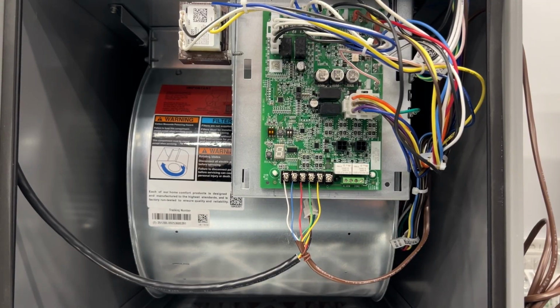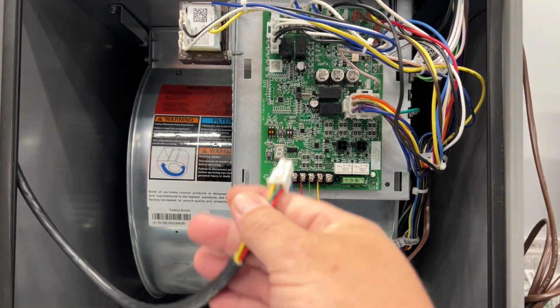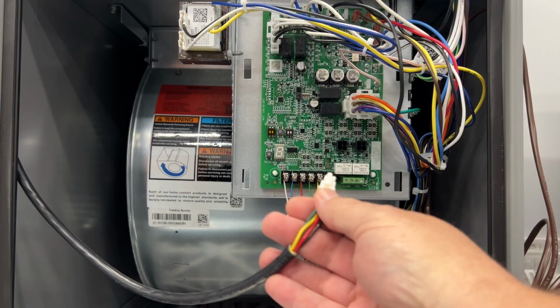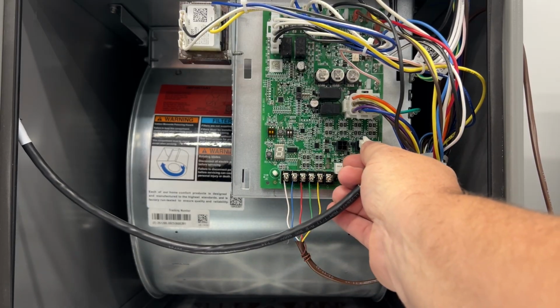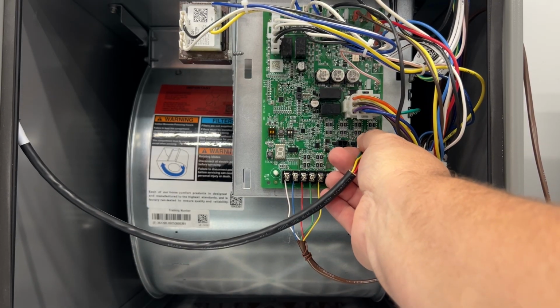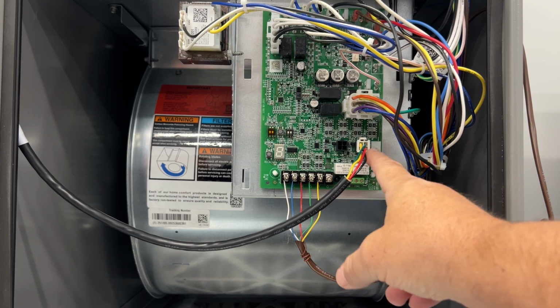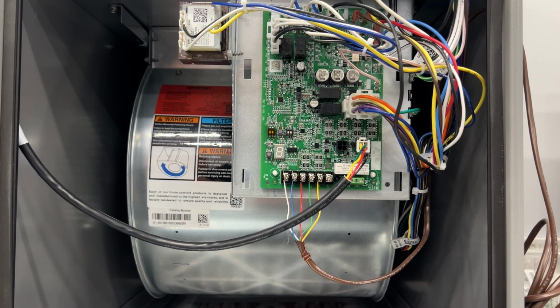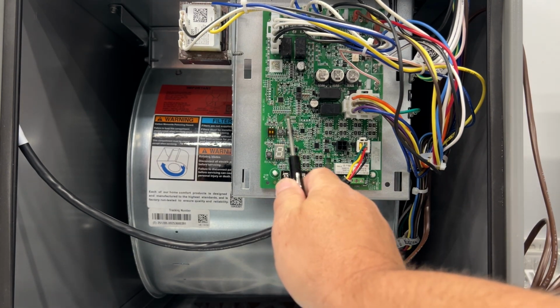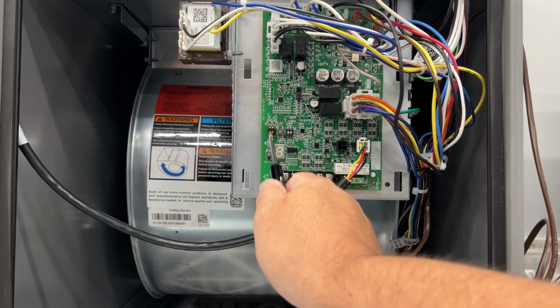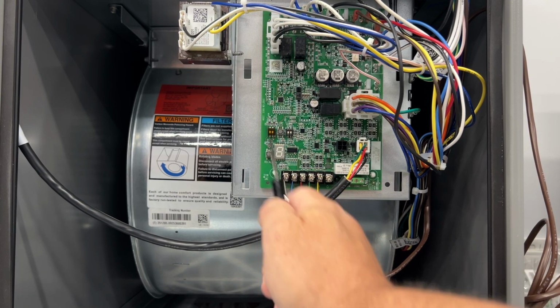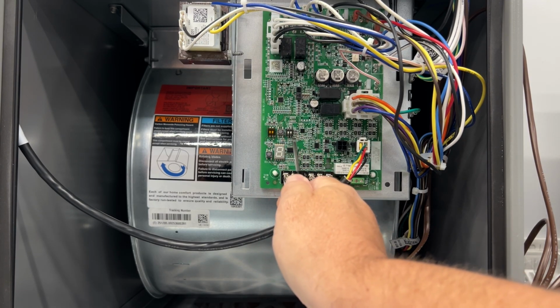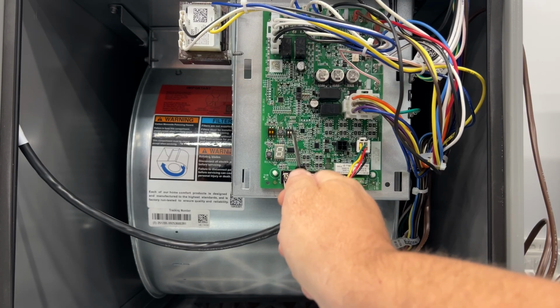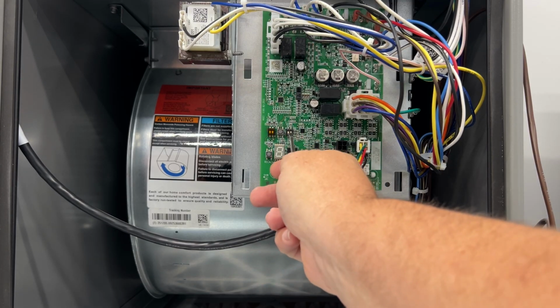Now, how we set this up, first of all, we're going to take the wire coming from this sensor in your evaporator coil, and we're going to place it on sensor 1 location, which on this particular board is on the right-hand side. And you'll notice we have 2 sets of dip switches. This first one here is going to control your fan delay, and this one over here is your low GWP sensor indicator switch.